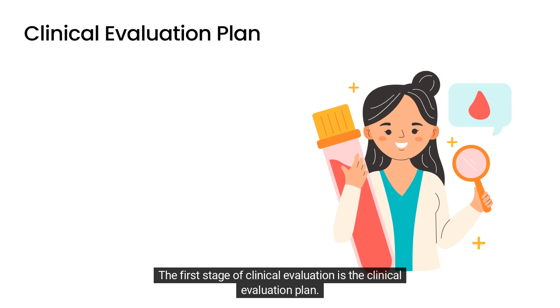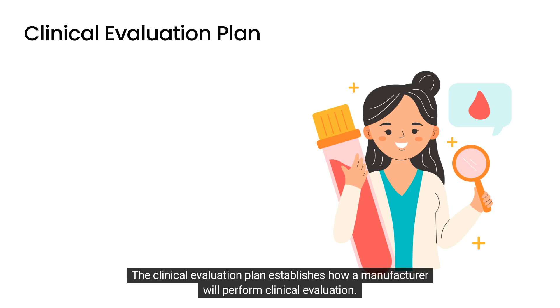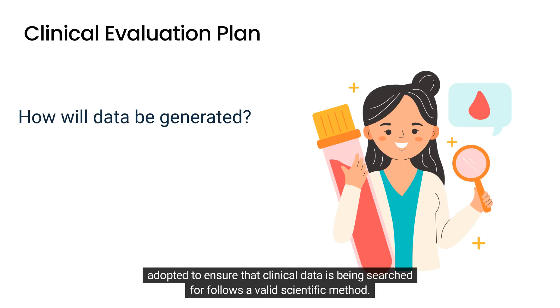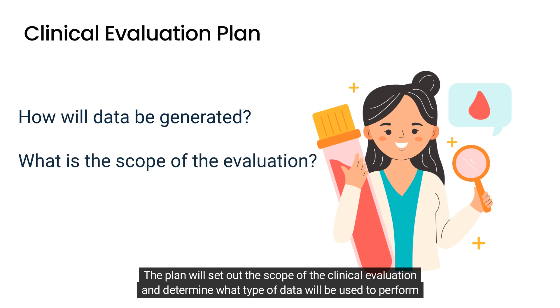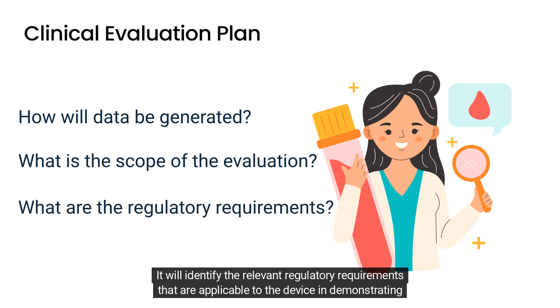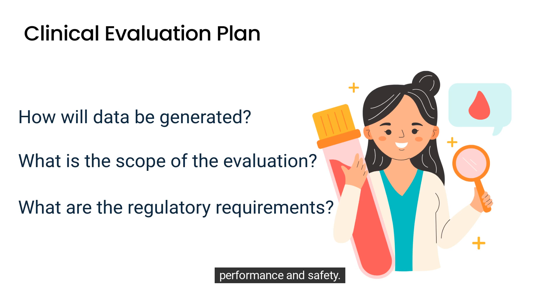The first stage of clinical evaluation is the clinical evaluation plan. The clinical evaluation plan establishes how a manufacturer will perform clinical evaluation. This includes how any scientific literature searches will take place and the methodology and research methods adopted to ensure that clinical data is searched for following a valid scientific method. The plan will set out the scope of the clinical evaluation, determine what type of data will be used, and identify the relevant regulatory requirements applicable to the device in demonstrating performance and safety.